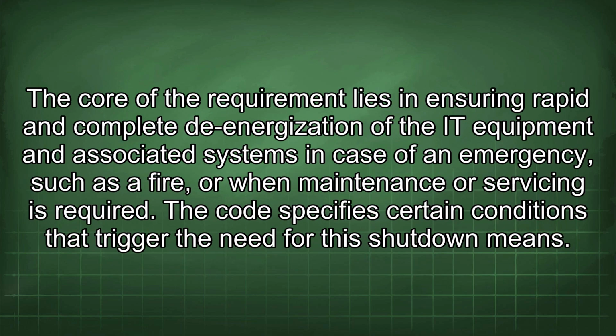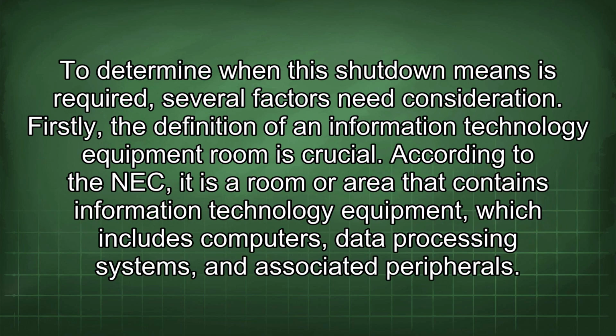The core of the requirement lies in ensuring rapid and complete de-energization of the IT equipment and associated systems in case of an emergency, such as a fire, or when maintenance or servicing is required. The code specifies certain conditions that trigger the need for the shutdown means. To determine when the shutdown means is required, several factors need consideration.